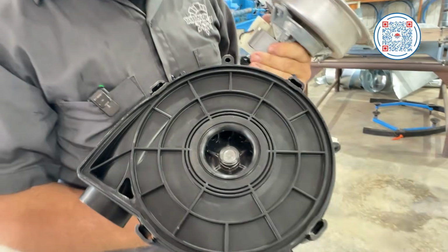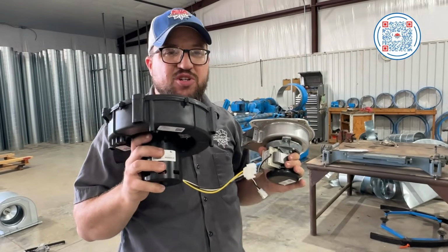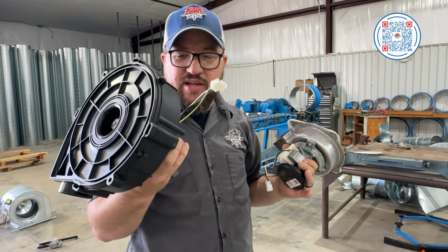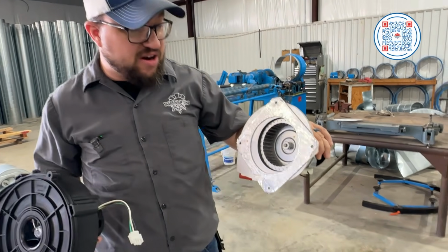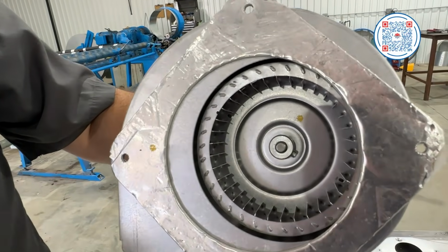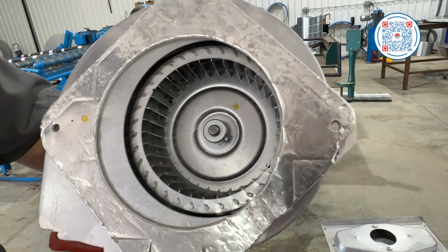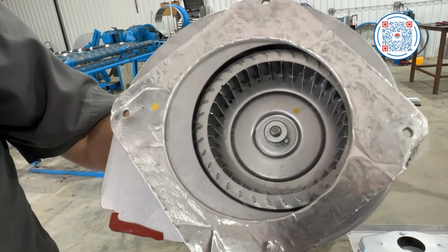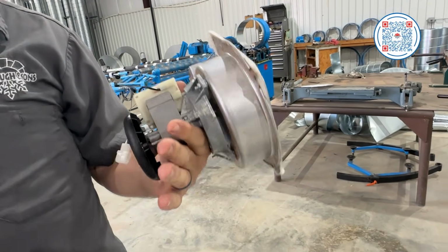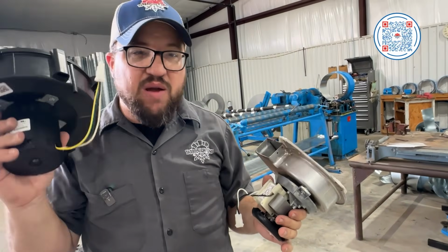At this point, we have condensation, so we want to make sure this is protected. If I had this right here on a 90% furnace, I'd have rust in the, well if not the first month, at least in the first year, and this thing would just fall apart. So we want to make sure we put the right motor on.